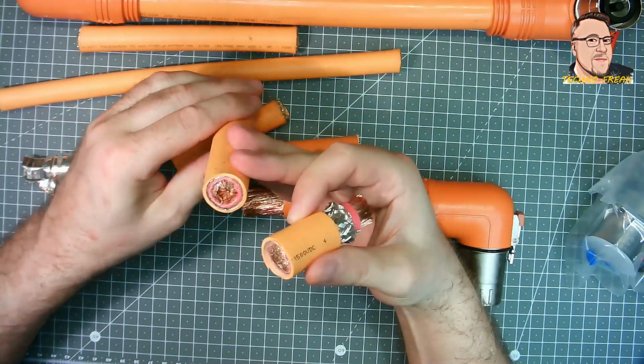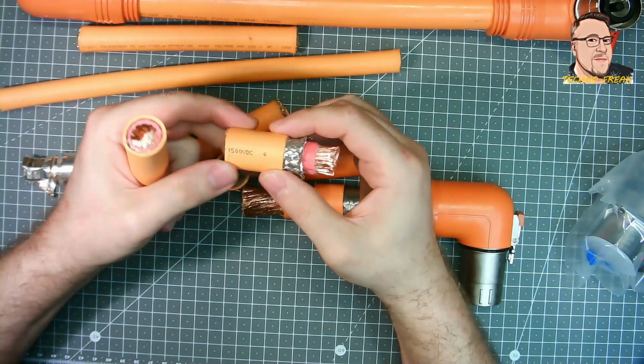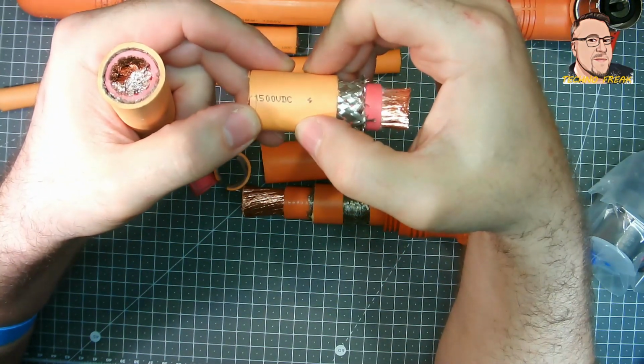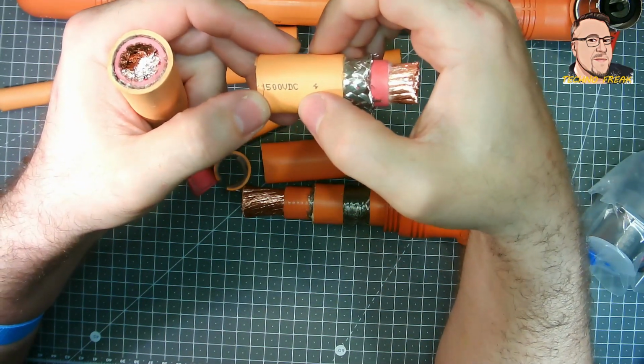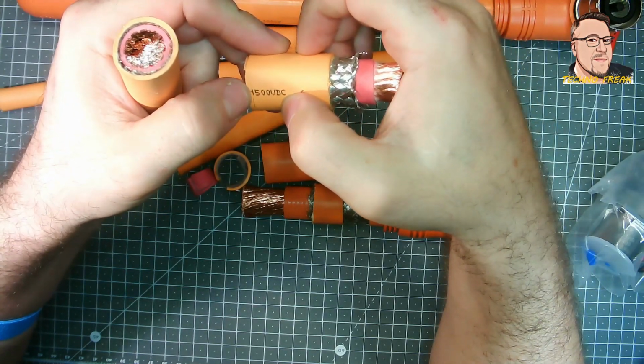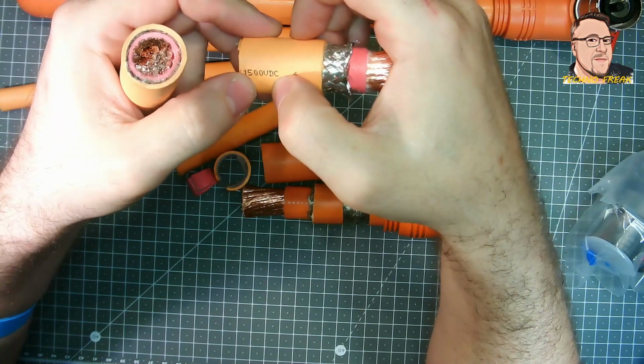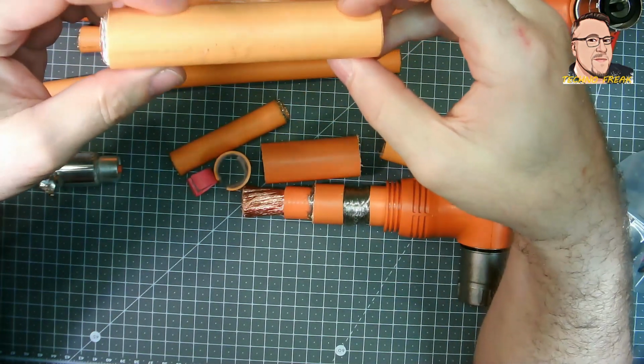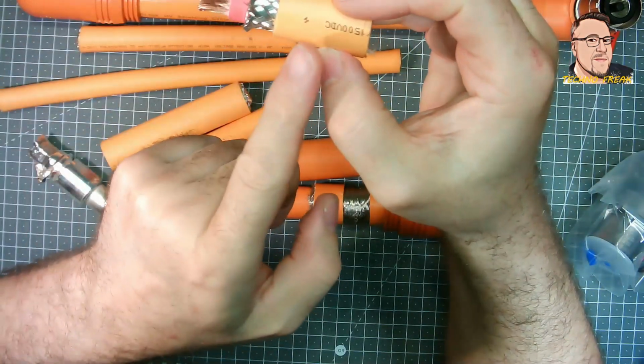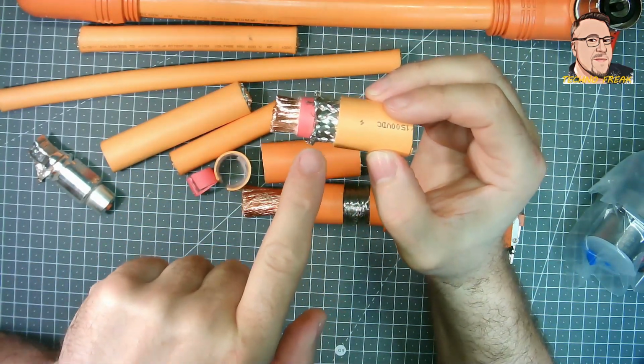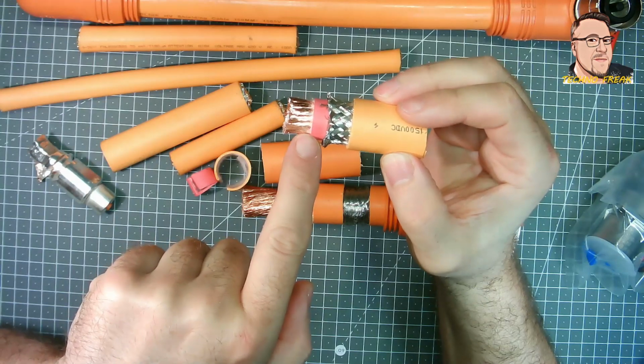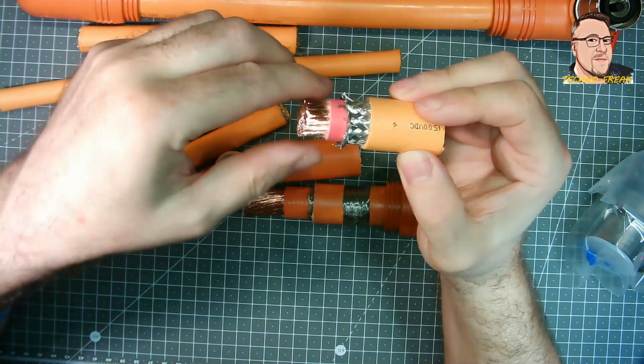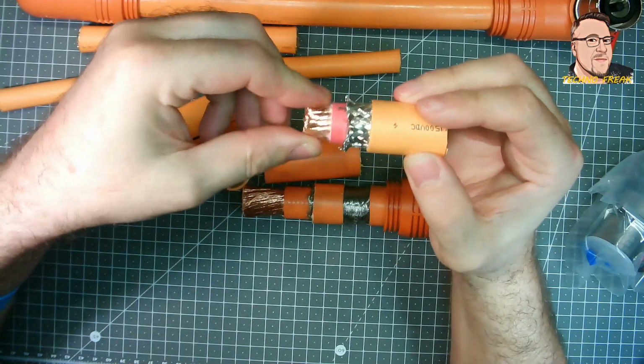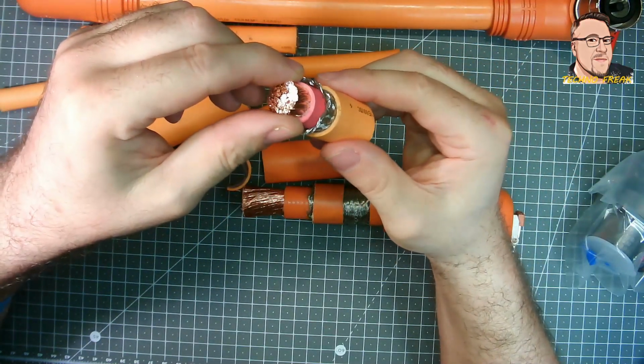Let's look at the other sizes. Voltage rating is again 1500 volts DC and the size this time is 120 mm square. A single core conductor of this size can handle up to 500 amps. Silicone insulation is designed to work with relatively high temperature. Plus, high purity copper reduces losses and voltage drop, which minimizes the heat generation.